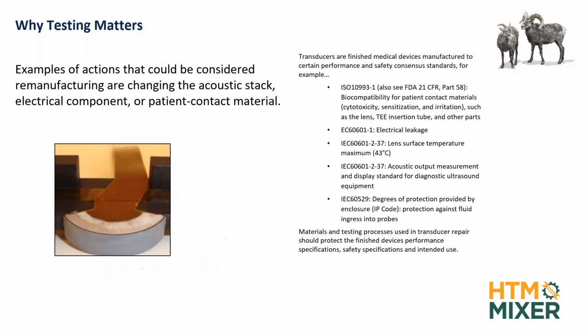And then the other one is the thermal, like I was talking about. The MI and the TI are displayed on the monitor of the ultrasound device as the sonographer is using it, and they are the control devices that you have to look at. So, examples of actions that could be considered remanufactured are changing the acoustic stack, electrical component, or the patient contact material. In addition, the FDA documents point you back to what the OEM is responsible for, in terms of standards that they need to follow and test to validate that their product is going to be safe and effective according to the guidelines.